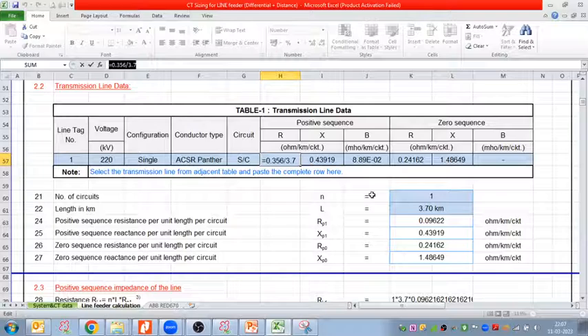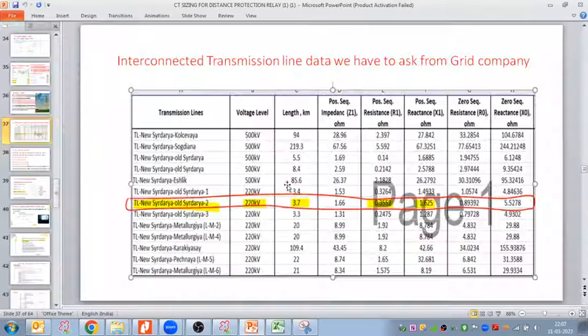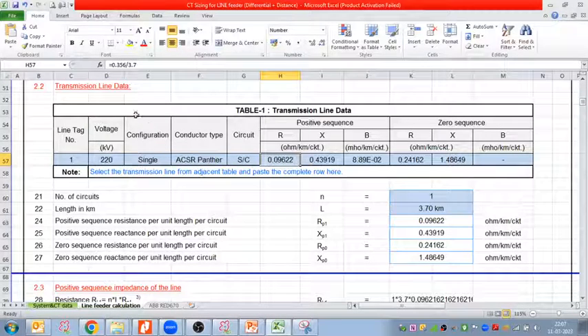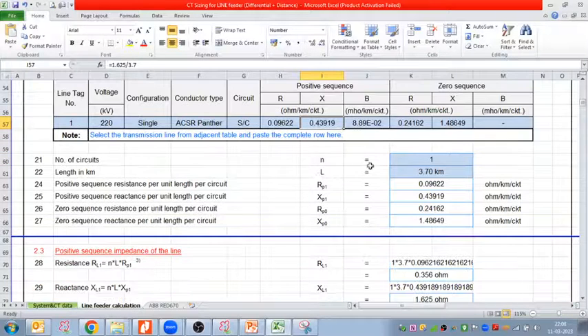The total resistance we have is 0.355, 0.356. So we calculated the per kilometer resistance here: the total resistance divided by the total length of the transmission line, 3.7 kilometers. It gives the R per kilometer or the X per kilometer. But if you are not converting to per kilometer, you can directly put the total resistance and total reactance; there is no need to convert to per kilometer, right?